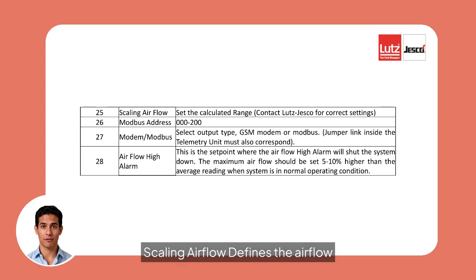Parameters 25 to 28 complete the configuration. Scaling airflow defines the airflow measurement range. Modbus address and modem Modbus select the communication settings for telemetry. Airflow high alarm sets the upper airflow limit, typically 5 to 10% above normal operating flow.